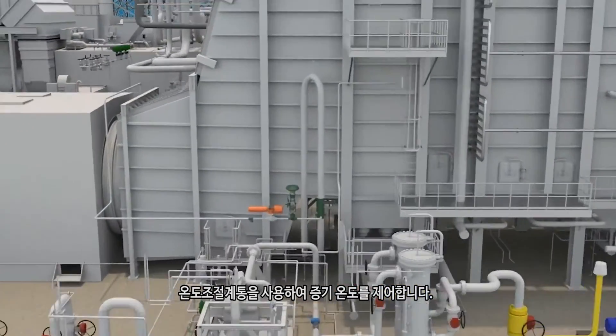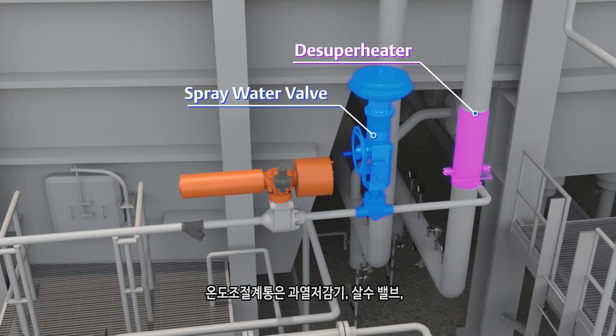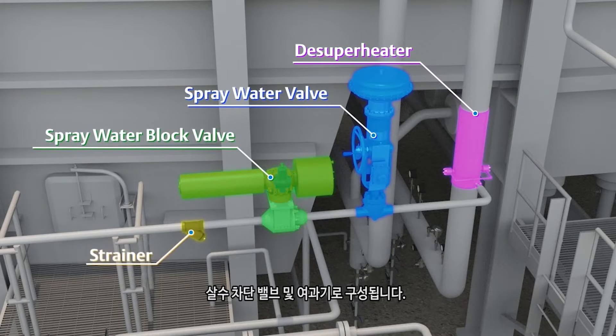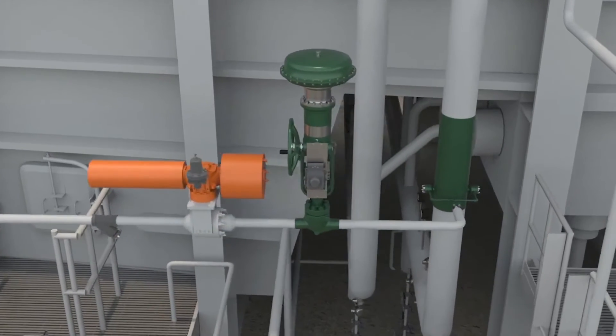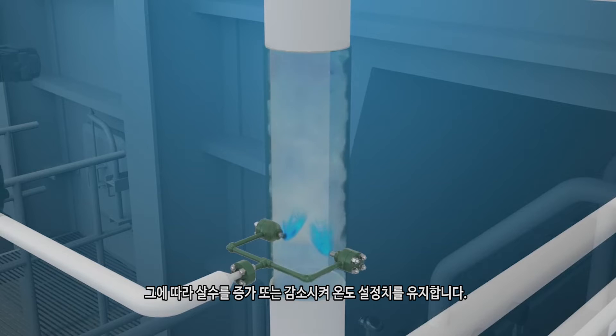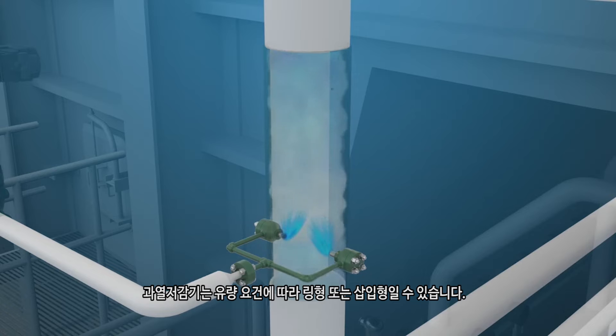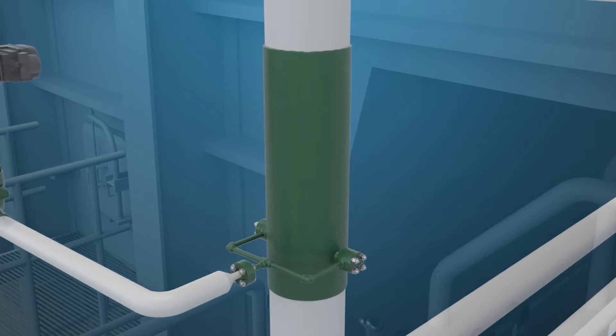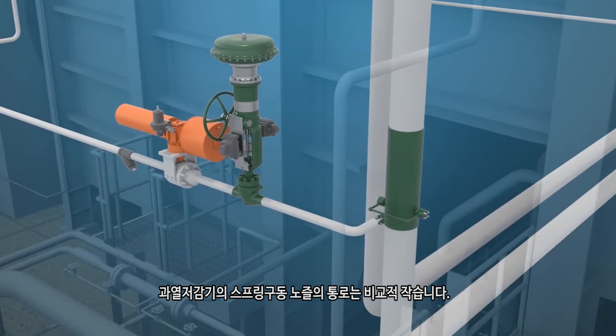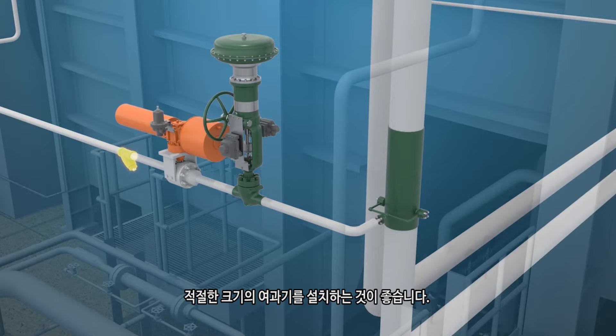Steam temperature is controlled using a attemperating system. It consists of a desuperheater, spray water valve, spray water block valve, and a strainer. The control system measures the temperature of the steam, compares it to setpoint, and then increases or decreases the spray water accordingly to maintain temperature setpoint. The desuperheater can be a ring or insertion style, depending upon the water flow requirements. The spring-loaded nozzles in the desuperheater have relatively small passages, and it is recommended that a strainer of suitable size be installed in the spray water line to prevent nozzle plugging.